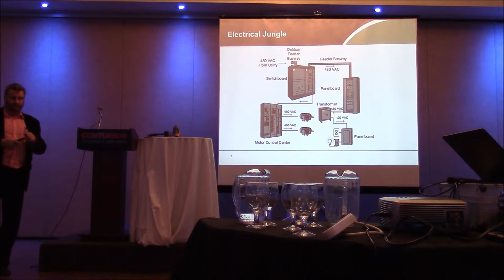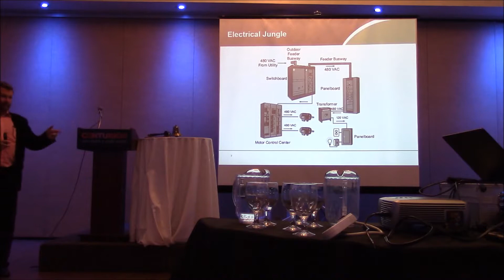So I had a project a number of years ago where it was a facility that only got shut down very occasionally. They knew they were doing the installation of a big chiller, and there was going to be cooling towers up on a roof. Part of my job was to take advantage of the upcoming shutdown and put in a breaker and cables in an existing switchboard to supply the MCC for the pumps that were going to run the glycol, cooling water, something in pipes up to the roof.